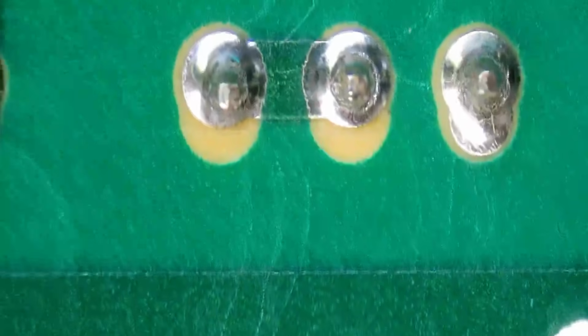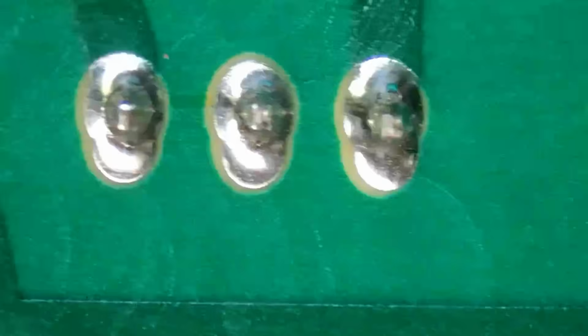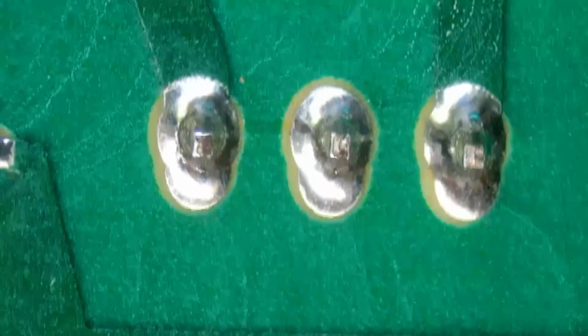Next, we're going to bring our attention to some of our other connections over here. These connections are the high voltage lines for the power to connect to the controller. Those can also fail with cracked joints. Next, here we have our transformer pins, which can also fail for the same reason. And actually, we're starting to see that on some of those pins. Now, when these connections on the transformer fail, they will cause a completely dead, no power symptom.